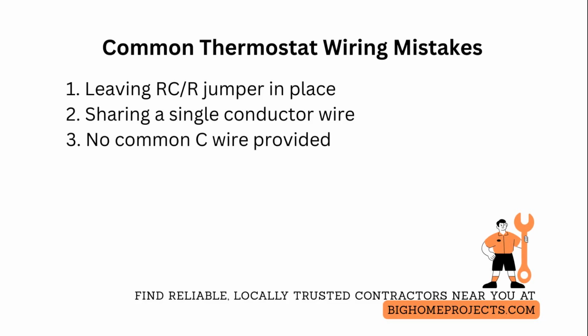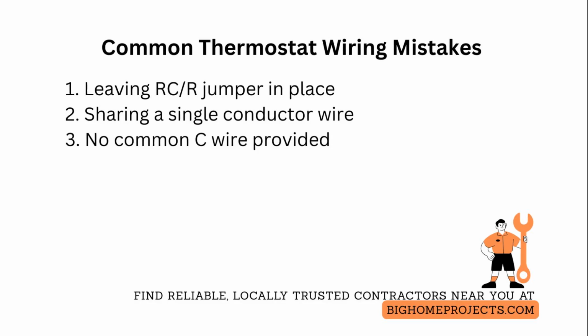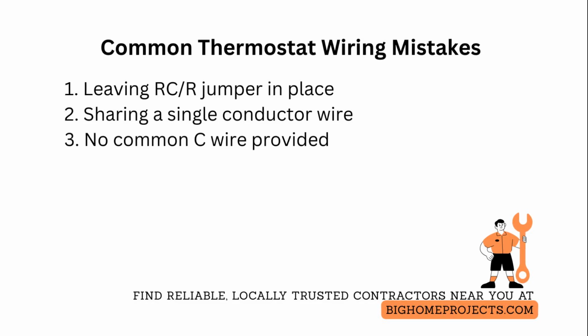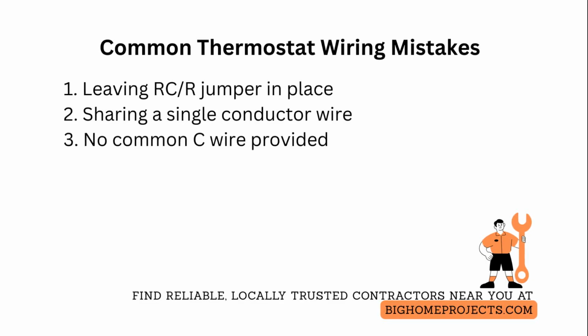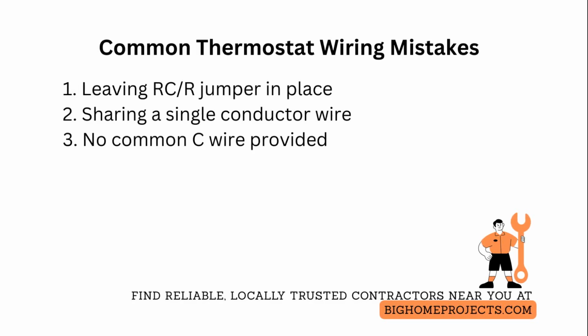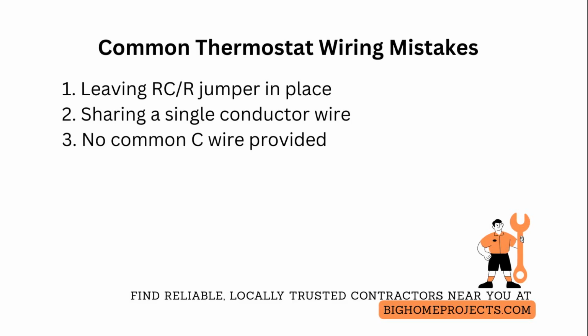The third frequent issue is failing to provide a common C wire for modern smart thermostats, resulting in thermostat rebooting and loss of Wi-Fi. Fix this by adding a C wire from one transformer through an isolation relay, or by installing a 5-terminal adapter or external 24 volt power supply matched to the system requirements.